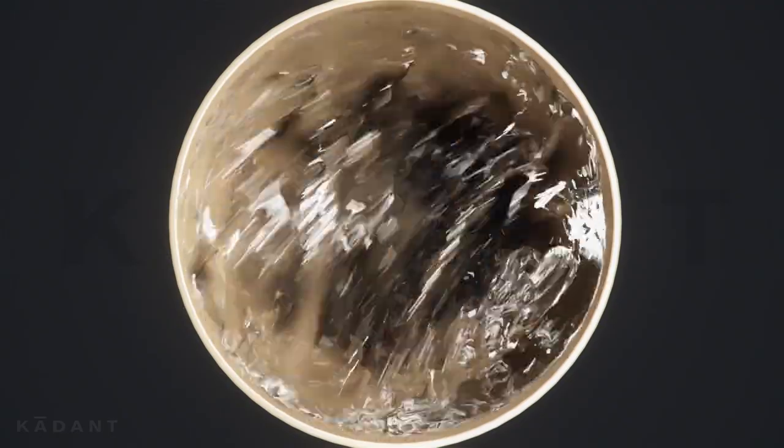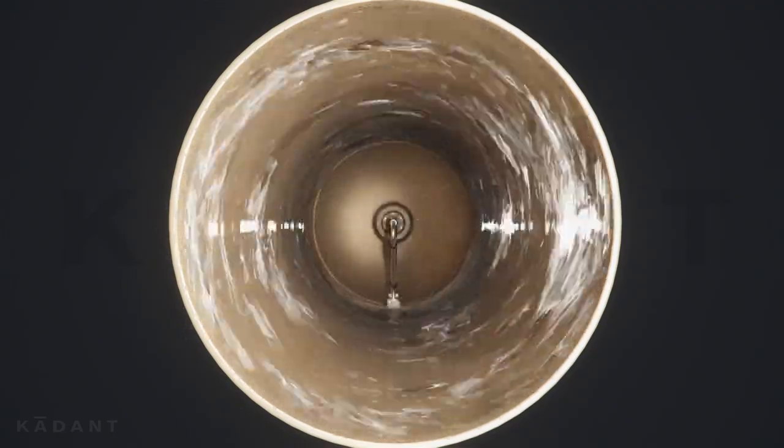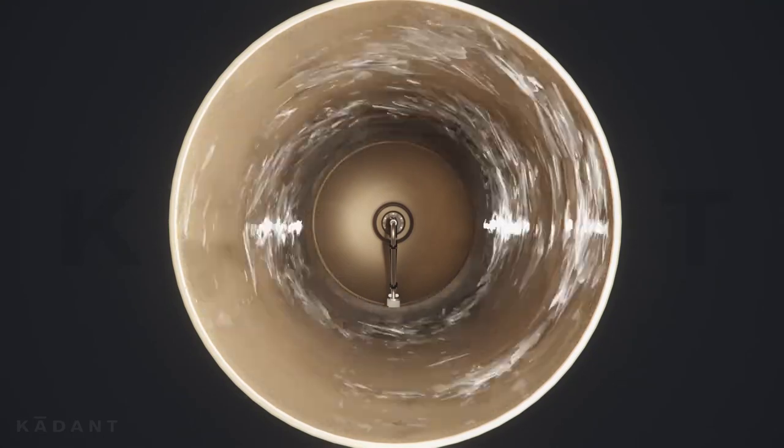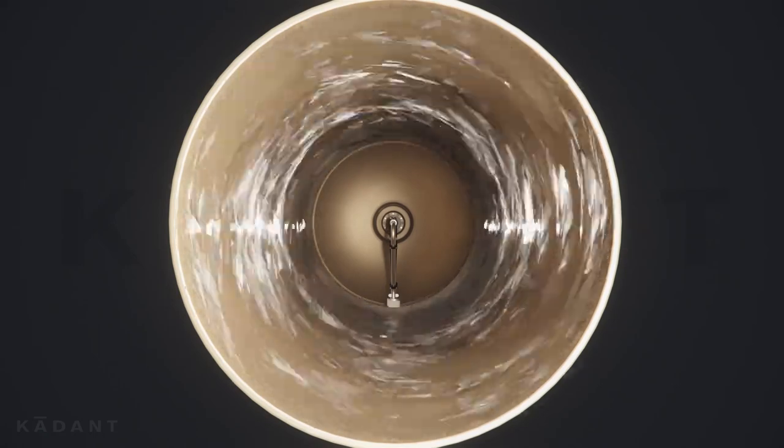As the dryer cylinder speed increases, centrifugal force will cause the condensate to rim. Rimming condensate forms an insulative layer between the steam and dryer shell, reducing heat transfer.